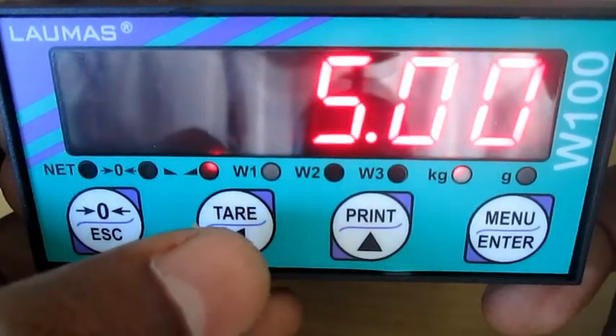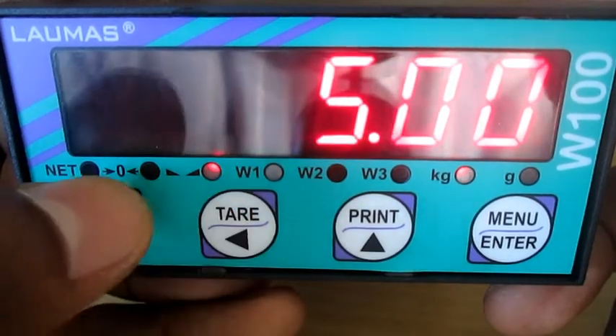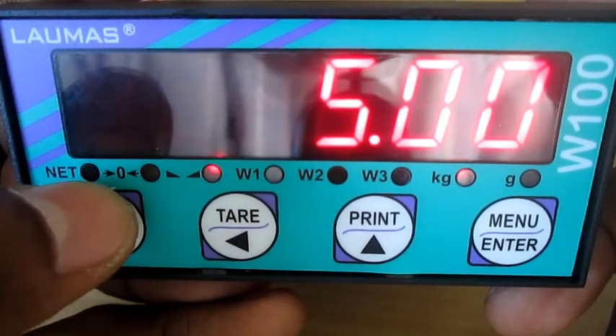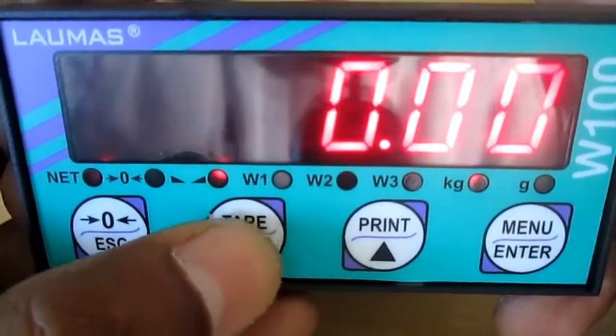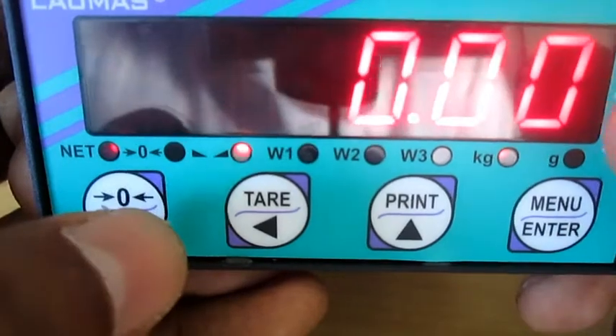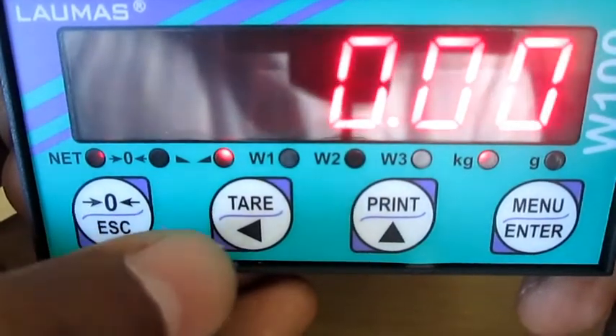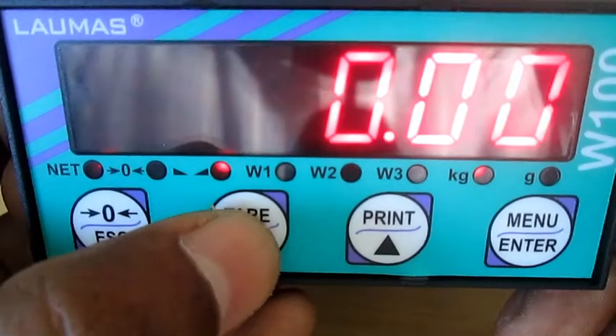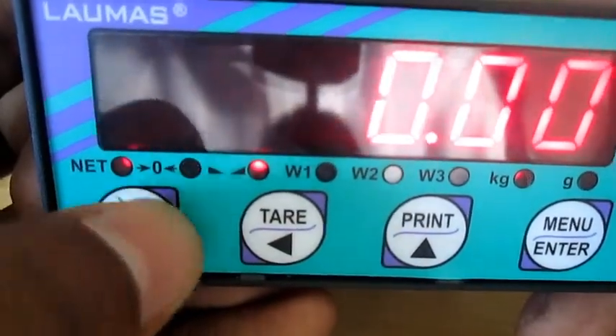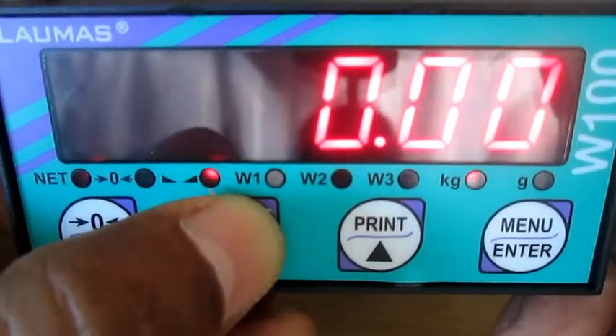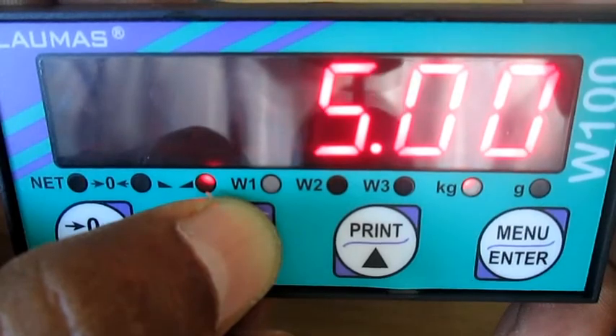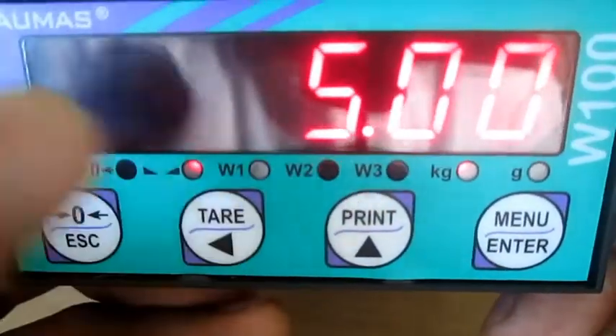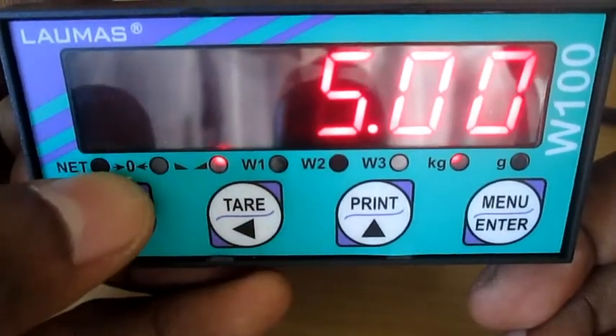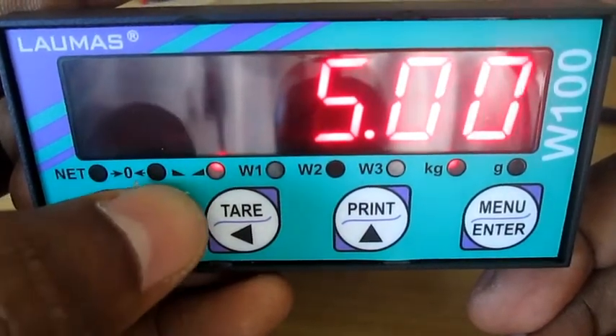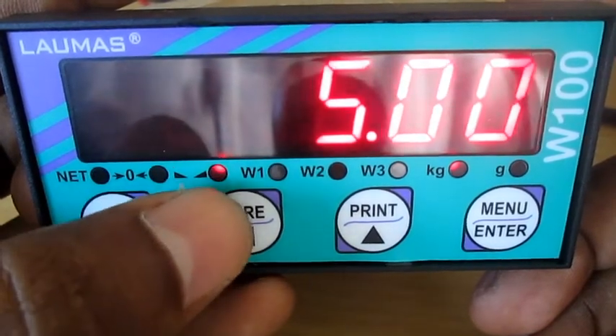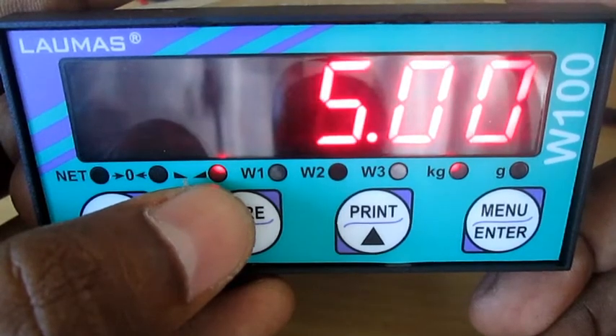Generally when you press tare once, the display will go to net mode. You can see here the net mode is not enabled. When you press tare button once, you will get net indication. See, parallelly the display goes to 0.0. But when you are bringing back to gross value, again that net indication will be disabled. You can see that I am pressing and holding for 3 seconds. That is important. Then the display will come back to gross mode. Okay, so the first one is net indication, second one is gross indication, third one is stable weight value indication.